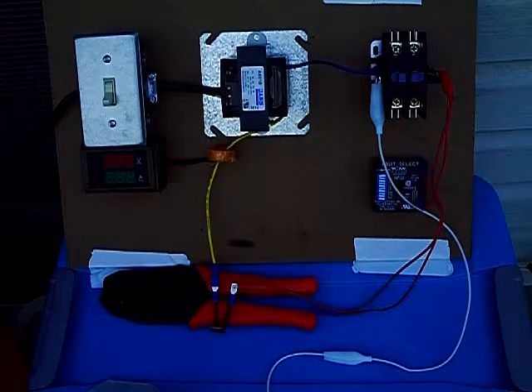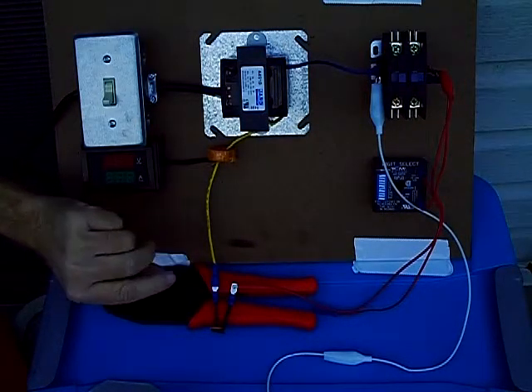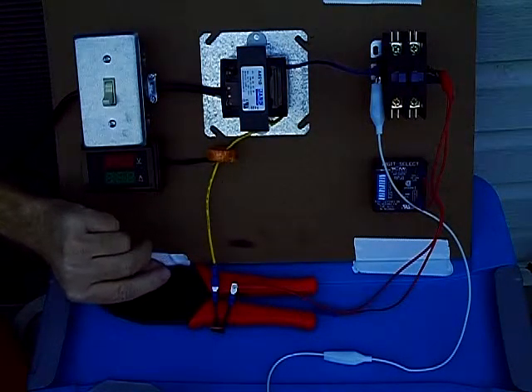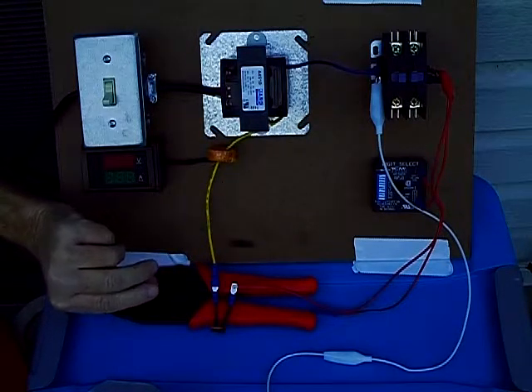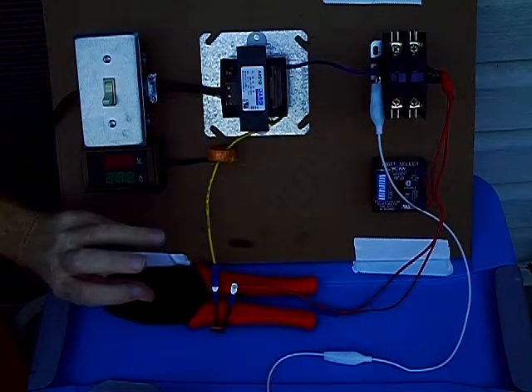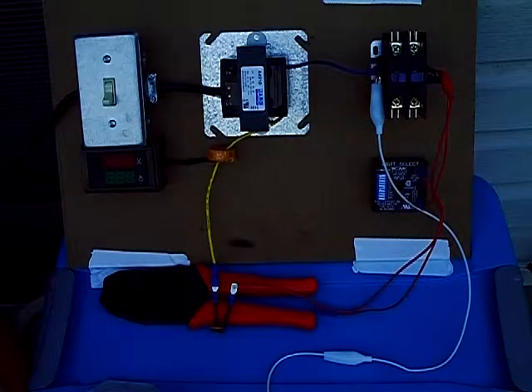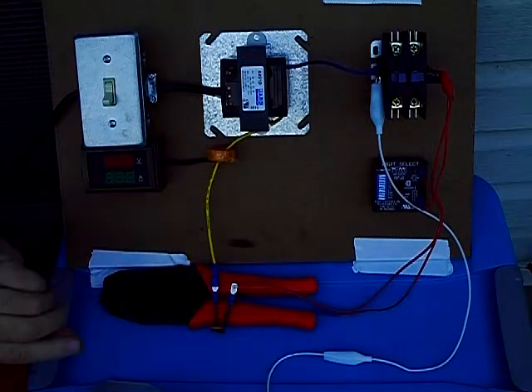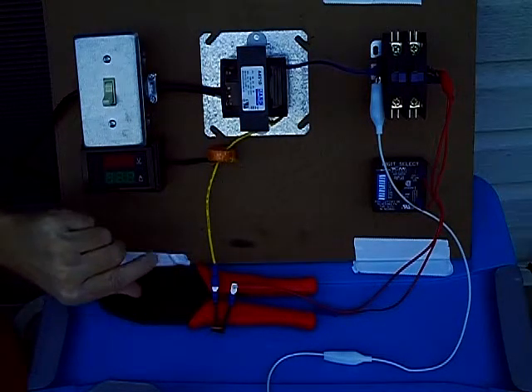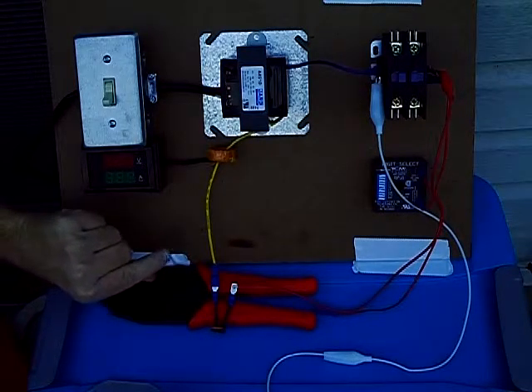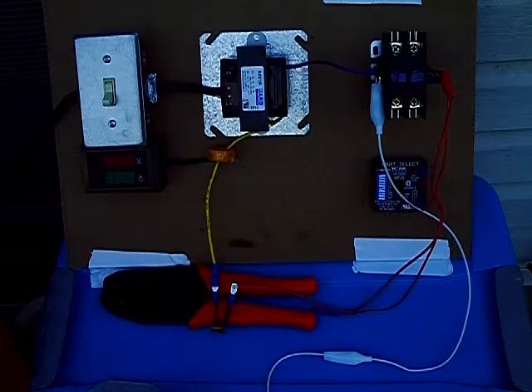That's because it's something called an intermittent short or an inrush. An intermittent short is when two wires short up against each other just momentarily, then separate and no longer have a short going across them, but that split second was enough to blow the fuse. When you get there and can't find it with the Short Pro tool, you put another fuse in there and it starts to work.